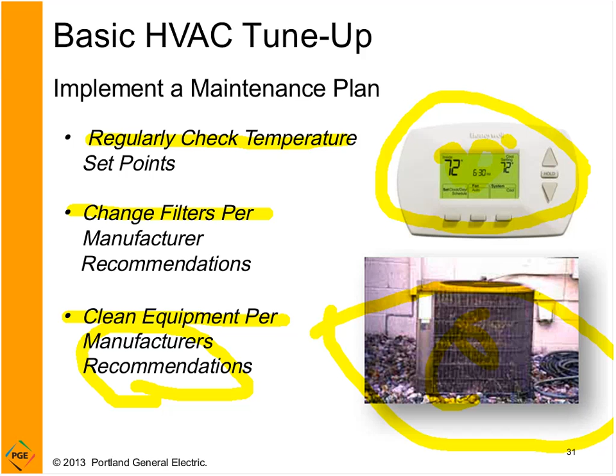You don't want to take a pressure washer to your condensing units. If you bend or break the fins, or damage the coils, it's going to affect the performance of your system. Cleaning this may save you energy, but more than likely it will help prolong the life of your equipment. It will save you energy—it just may not show up on your utility bill, depending on your consumption patterns.